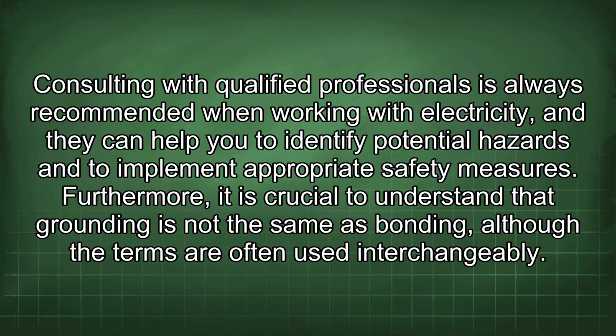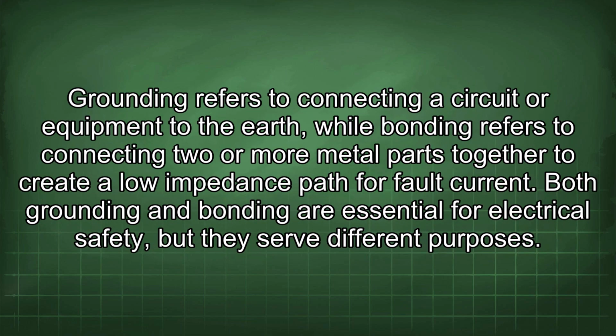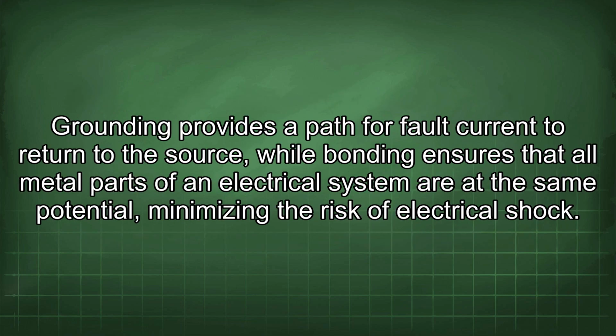Furthermore, it is crucial to understand that grounding is not the same as bonding, although the terms are often used interchangeably. Grounding refers to connecting a circuit or equipment to the earth, while bonding refers to connecting two or more metal parts together to create a low impedance path for fault current. Both grounding and bonding are essential for electrical safety, but they serve different purposes. Grounding provides a path for fault current to return to the source, while bonding ensures that all metal parts of an electrical system are at the same potential, minimizing the risk of electrical shock.